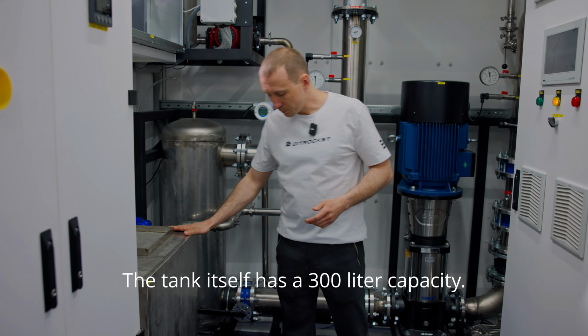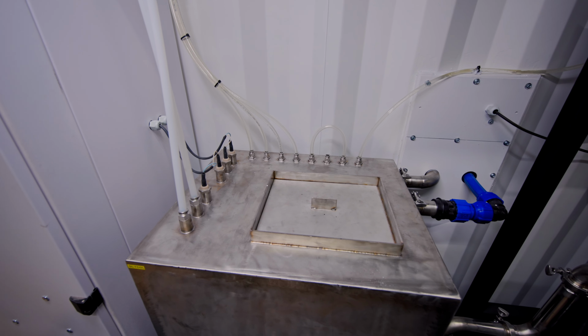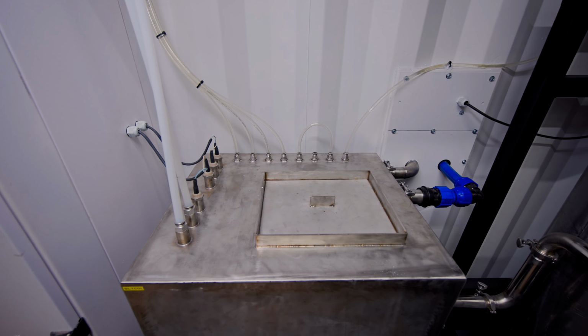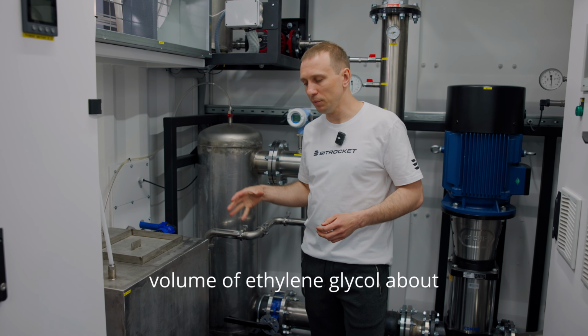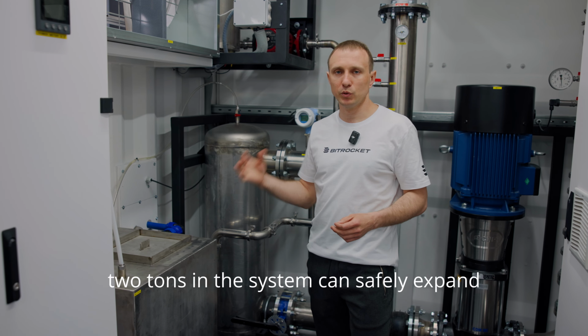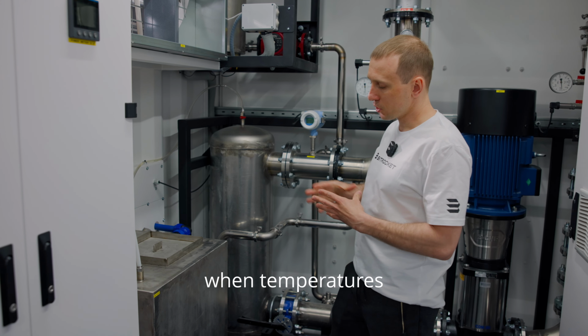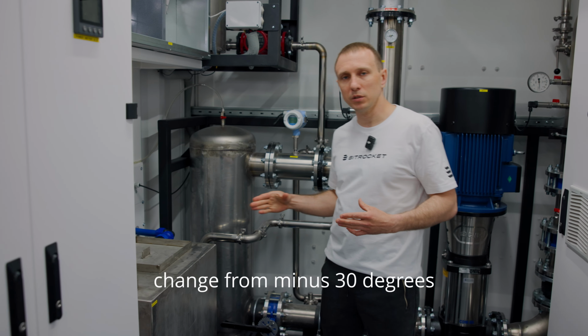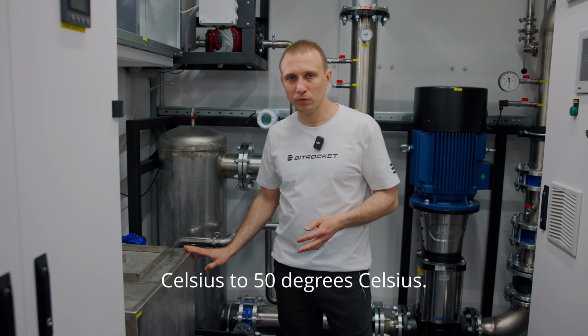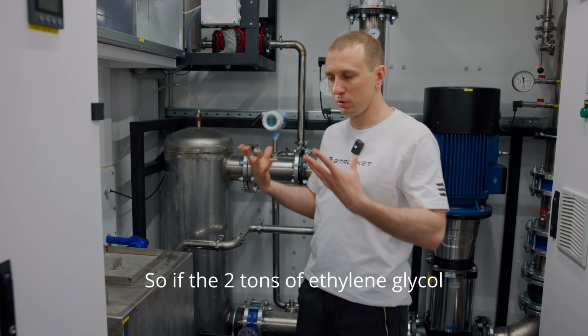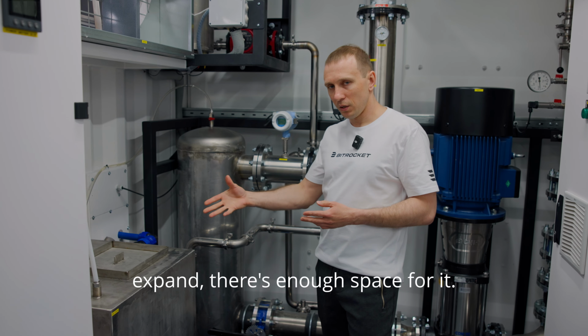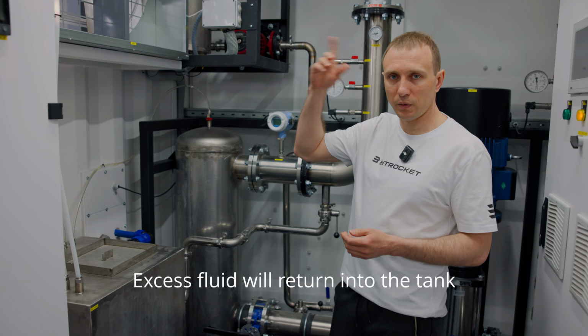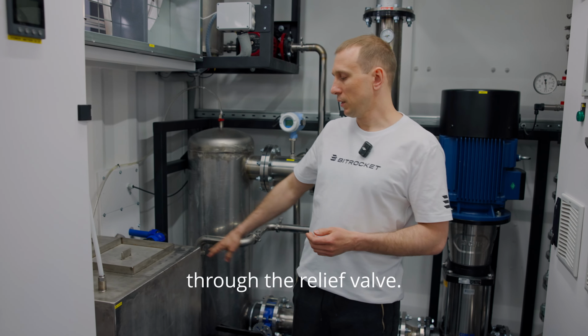The tank itself has a 300-liter capacity. It has minimum and normal level markers, designed so that the volume of ethylene glycol, about 2 tons in the system, can safely expand when temperatures change from minus 30 degrees Celsius to 50 degrees Celsius. So, if the 2 tons of ethylene glycol expand, there's enough space for it. Excess fluid will return into the tank through the relief valve.